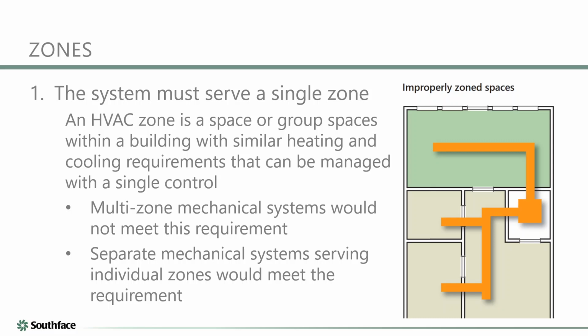Yeah, this is our first requirement. The HVAC systems must serve a single zone. This is relatively straightforward. Multi-zonal equipment becomes complicated in terms of how it is controlled and how it's delivering airflow to the different spaces within the building. If you look at the little graphic on the screen, you can imagine that the one large room there might have a very different cooling demand than the small office located adjacent to it. So having 3 or 4 different zones of your building all connected to one piece of centralized equipment is going to require more complicated controls and more complicated ducting to try and provide adequate comfort in each one of those zones.